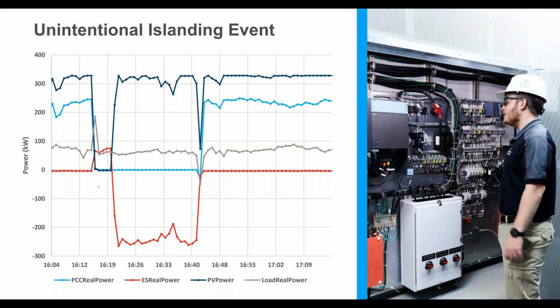Once the solar dropped, the energy storage picked up the load. The red line, energy storage, picked up the load immediately for the next 5 minutes before the solar came back online. When the solar came back online, energy storage went into charging mode. Even though energy storage went into charging mode, it continued to form the grid. So energy storage was regulating the voltage and frequency, and that's because solar inverters cannot regulate frequency because of the intermittent nature of solar. So energy storage was forming the grid, solar was providing the power.